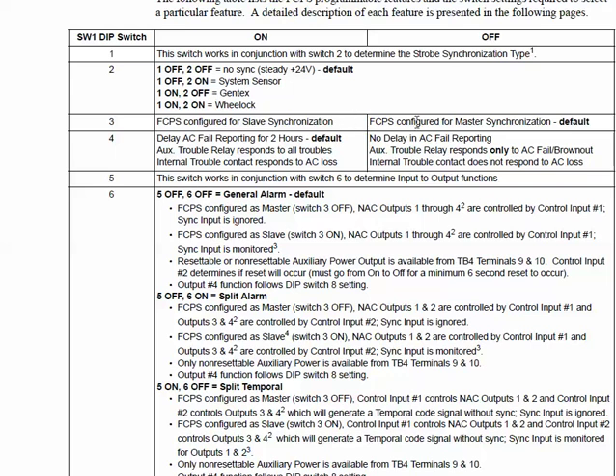If that DIP switch is off, then the FCPS is set as the master, and it's going to create its own. So if you look at switches 1 and 2, those tell the outputs how they're going to behave. If both of them are off, then there is no sync.